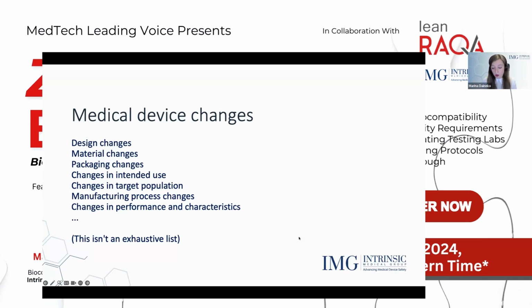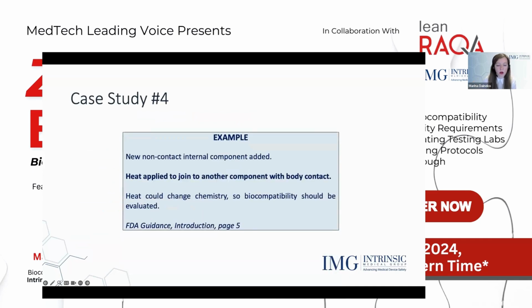And just a quick actual example, it's my favorite one, and I take it from the FDA guidance. They just have it within this guidance that, for instance, there is a medical device and we are adding internal components that have no contact with the patient. What does it mean for us? If we follow the standard, we should not perform biocompatibility, right? But there is a trick here, because to be able to apply this component during the manufacturing process, heat is applied to join it to another component, and this other component has contact with the body. And from this perspective, we have to re-evaluate our biocompatibility, to do biological assessment, just to understand whether there is any effect from applying heat in this manufacturing process to our device.